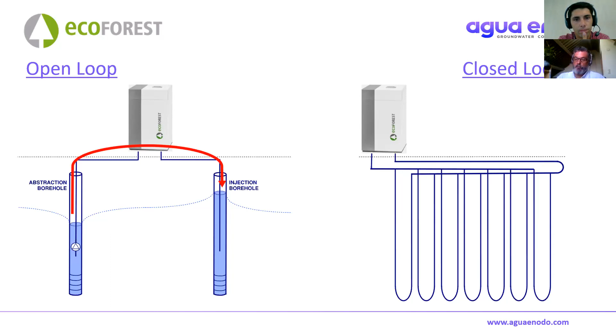Just to make sure we're all on the same page, open loop requires some source of water which we take to the heat pump, and then we reject that water. In many systems, that's via wells, via boreholes, to and from an aquifer. With closed loop, we're talking about some circulated fluid within a pipe in the ground, typically horizontal or vertical.